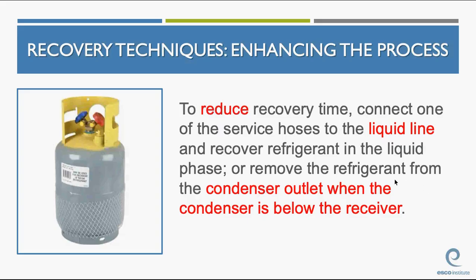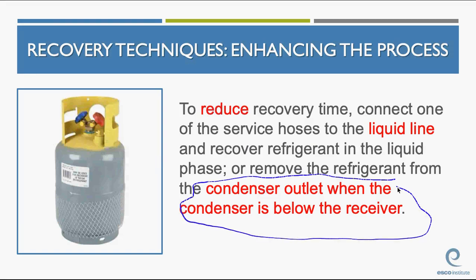Okay, this last statement's extremely important. This is on your test. If the condenser outlet is below the level gravity-wise of the receiver, remove the refrigerant from the condenser outlet. Otherwise, remove the refrigerant from the liquid line. Any questions on this slide? I'm trying to picture that.